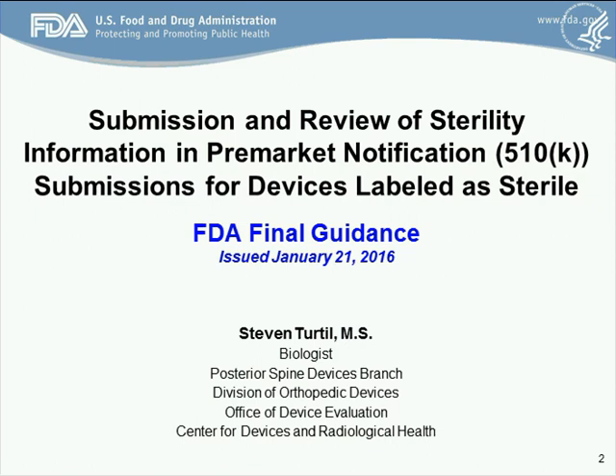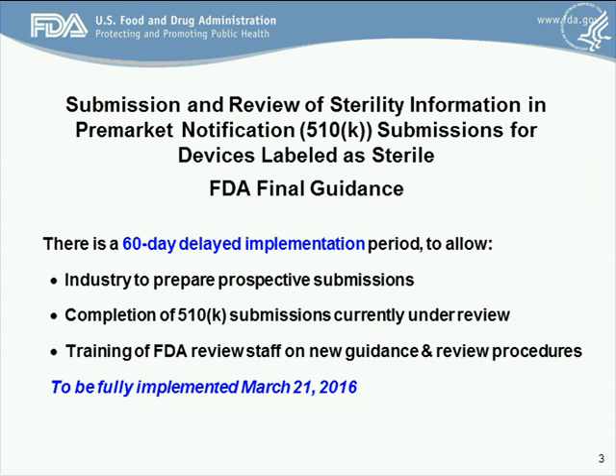Good afternoon, everybody. Welcome, and thank you for joining us this afternoon. My name is Steve Turtel. I'm a biologist for the Division of Orthopedic Devices, and the subject of today's webinar is the new guidance, Submission and Review of Sterility Information in Premarket Notification Submissions for Devices Labeled as Sterile. This was issued on January 21, but I want to bring immediately to your attention that there is a 60-day delayed implementation period. This is to allow industry to prepare prospective submissions, to allow for completion of 510K submissions currently under review, and to allow for training of FDA review staff on new device guidance and review procedures. So this will be fully implemented on March 21, 2016, and all new submissions received on or after March 21 will be subject to the new guidance document.